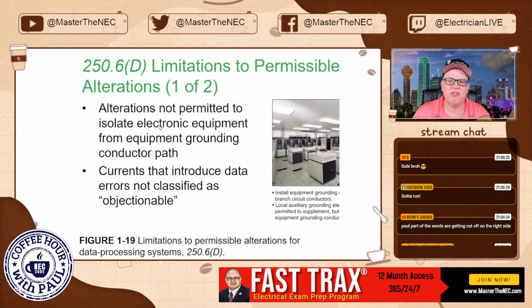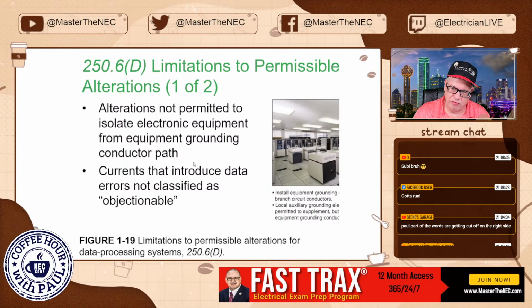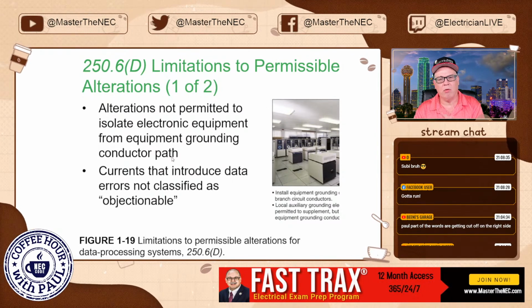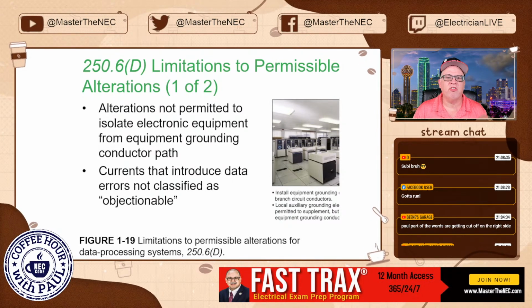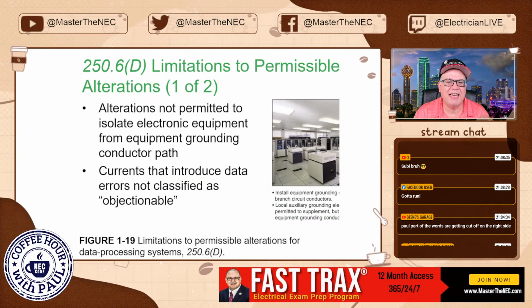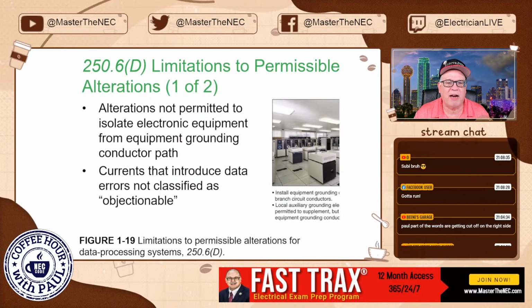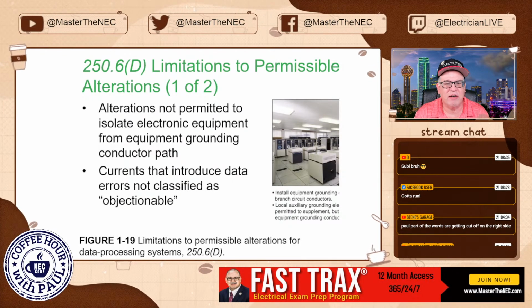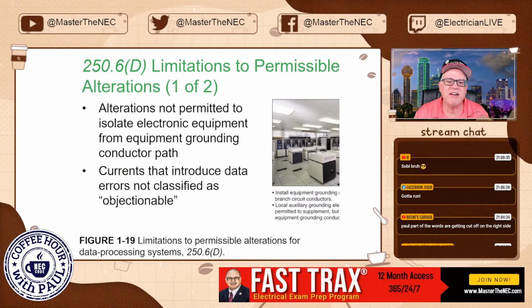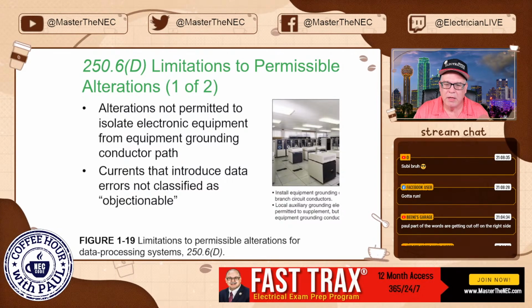250.6D, limitations to permissible alterations. All right, okay, so alterations not permitted to isolate electronic equipment from equipment grounding conductor path. Currents that introduce data errors are not classified as objectionable. Now, let me explain something.